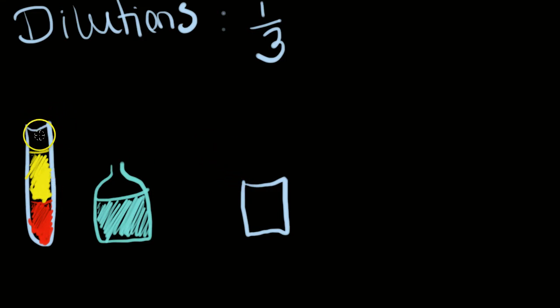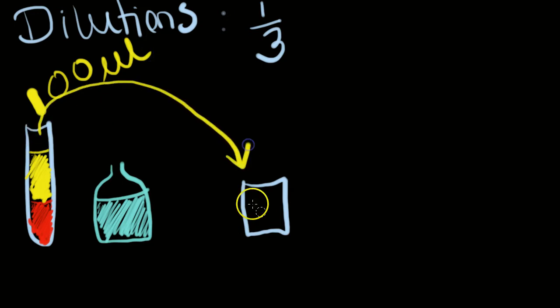The first thing you would do is get some sample out. Let's say we're going to get 100 microliters out, and we're going to take it and put it right here, 100 microliters of your plasma or serum into the sample cup.